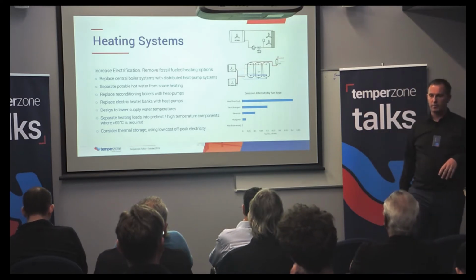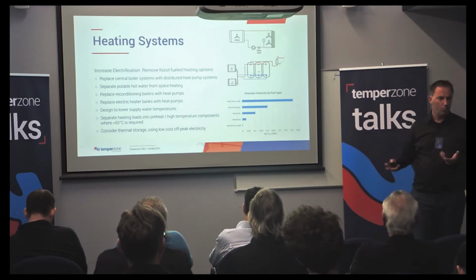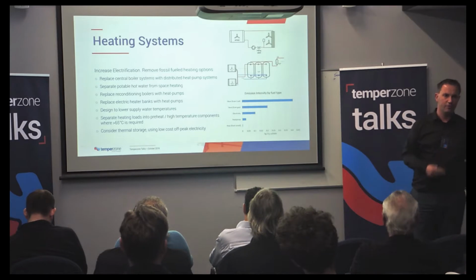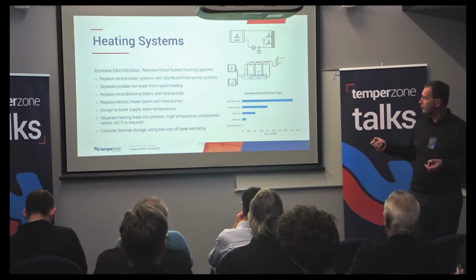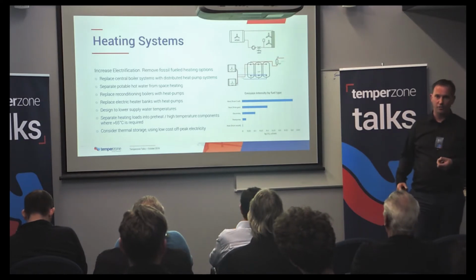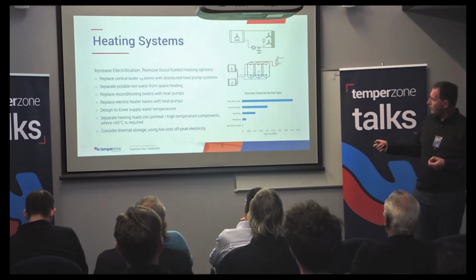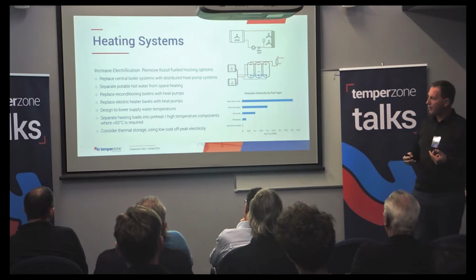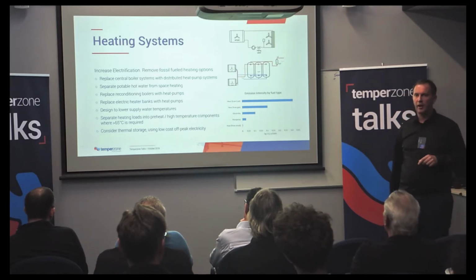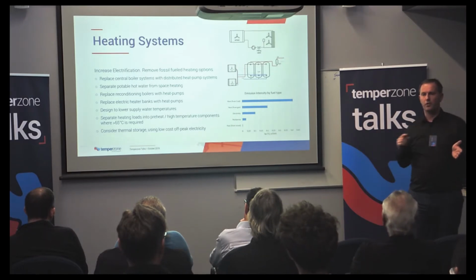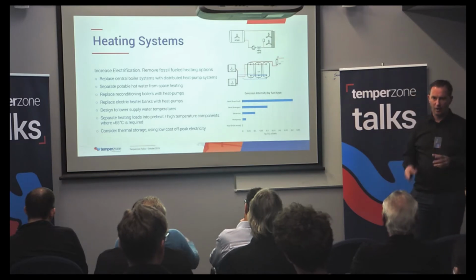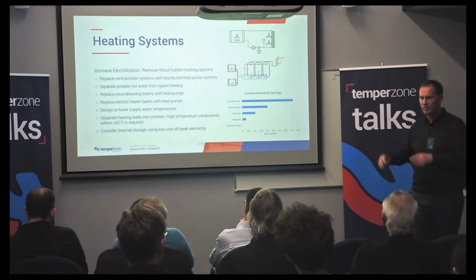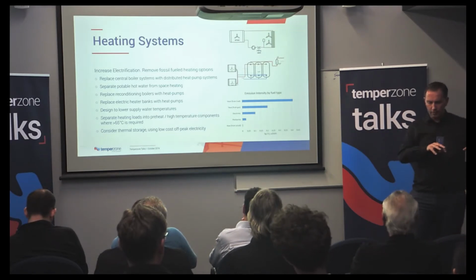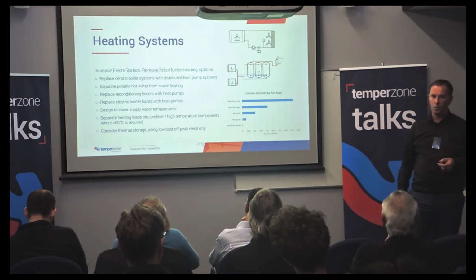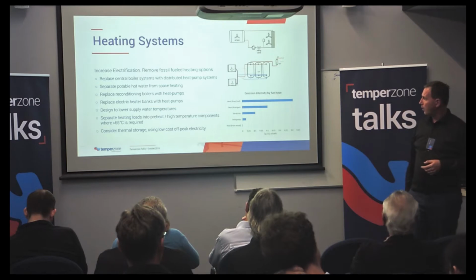The stationary energy is really the low-hanging fruit with this. It's a relatively easy thing to get rid of fossil fuel out of buildings. And we see refrigeration systems as being one of the most energy efficient ways of doing this. So looking at different ways you can do this, replacing central boiler systems with a distributed heating system. So rather than driving your primary circuit at the highest temperature that your building requires, split that up into potable water, into space heating, and supply those loads separately from the appropriate type of heat pump, rather than having it all in one primary with the exchanges on the secondary side.